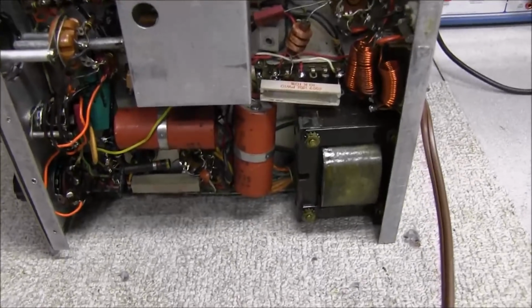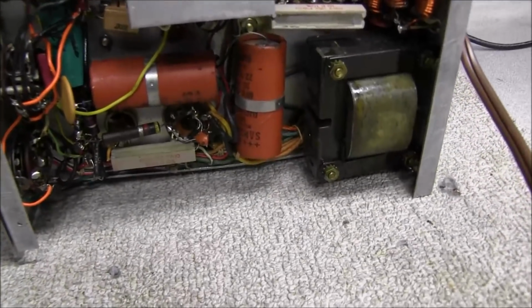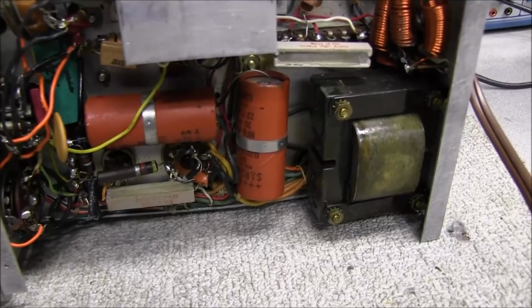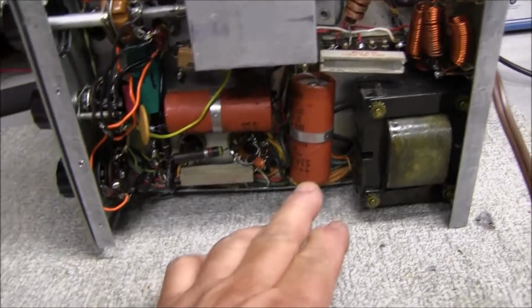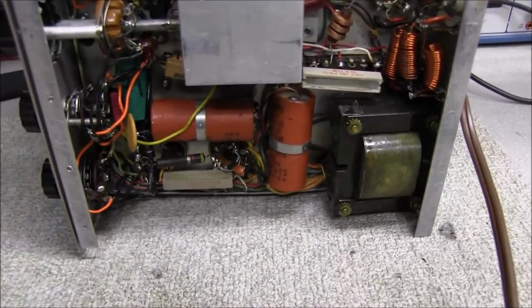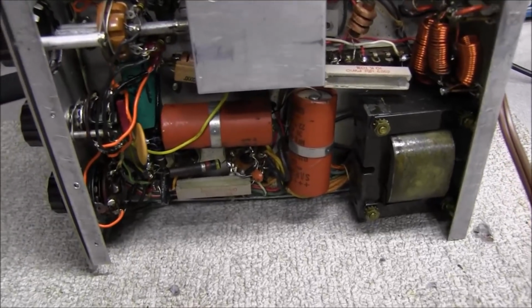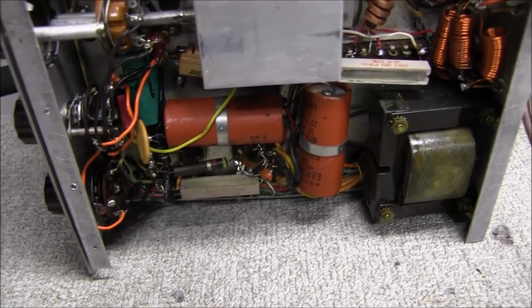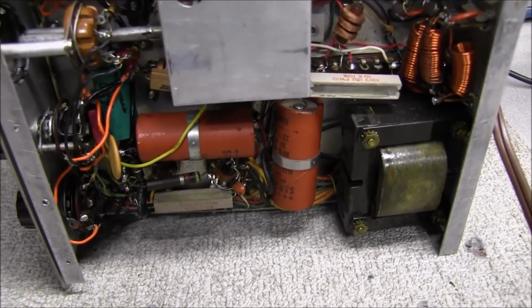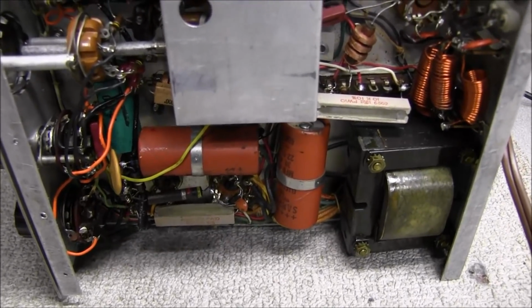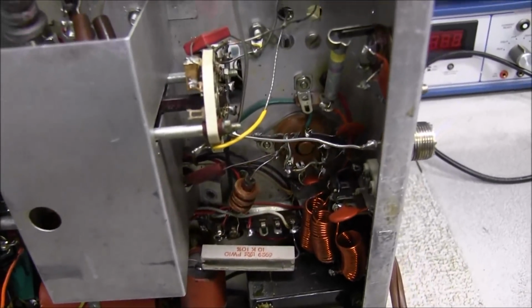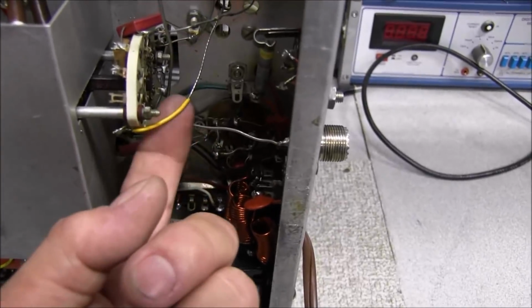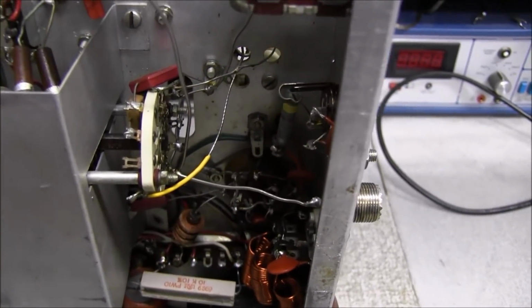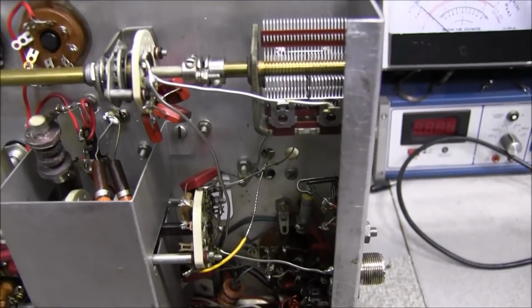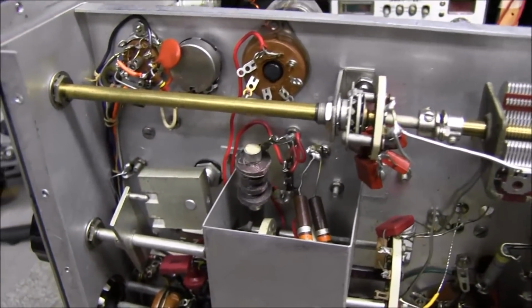So we look here under the bottom, we can see we got the original filter capacitors in. So this will be the first thing we need to change out. You never want to fire them up with these old crusty capacitors in there, because it can cause a problem. Strange looking here, there's a yellow wire with some of the insulation missing off of it, but other than that, it really, really looks good.